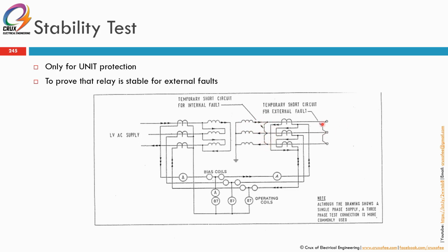So this is for outzone protection. For outzone, we inject outzone. You inject from this side, and then you short on the LV side, before the CT of the secondary or the primary. Then you will check whether it's stable or not. So this is for differential CT, differential protection.